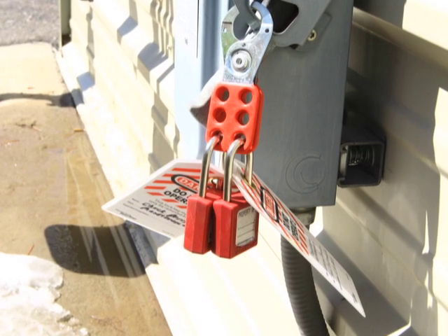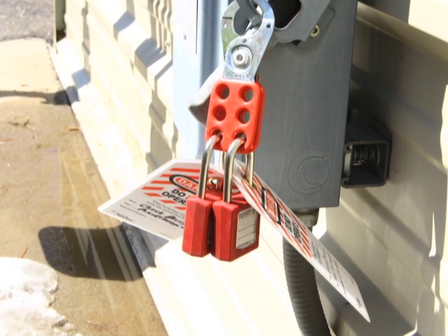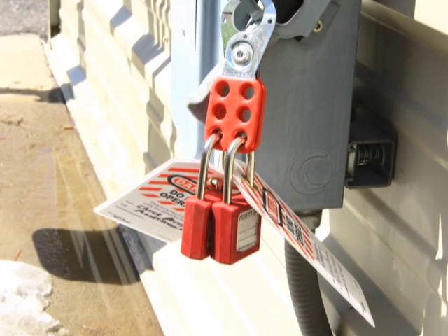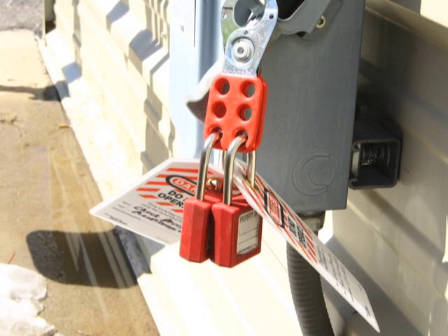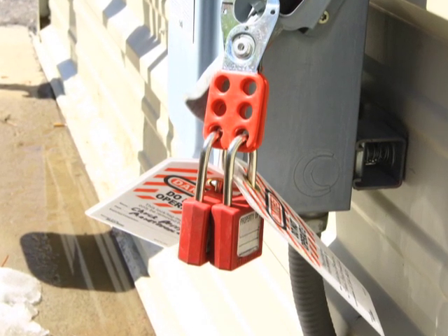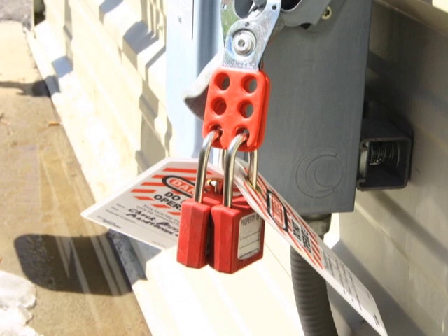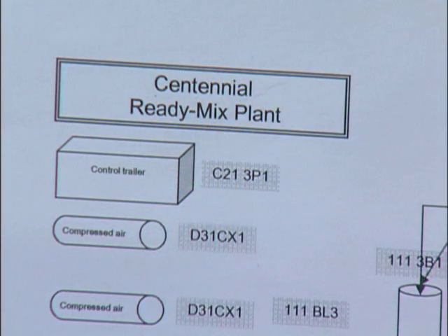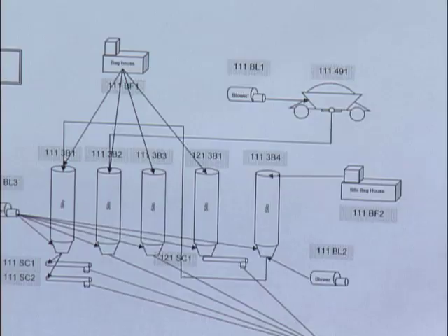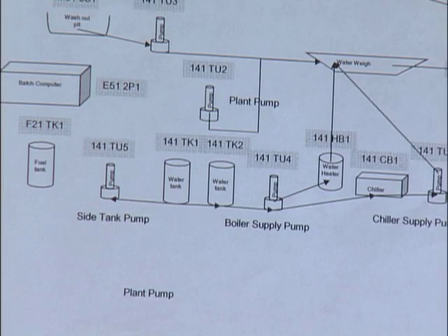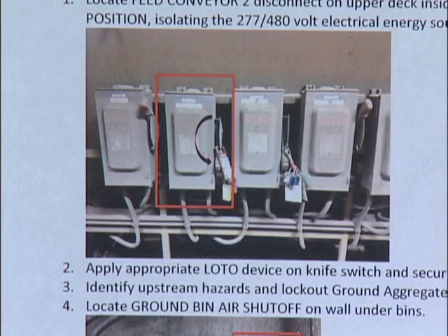Number 2. Make sure that all valves, breakers, and electrical panels have the ability to be locked out and tagged out. If not, when they are replaced or modified, then make sure they will accept lockout-tagout devices. Number 3 is for you to draw a layout of the facility and equipment at the facility. Check with your engineering department for blueprints or modified as-builts. Show the locations of all machinery and equipment in the facility. Illustrate the locations of all electrical breakers, control panels, and valves.